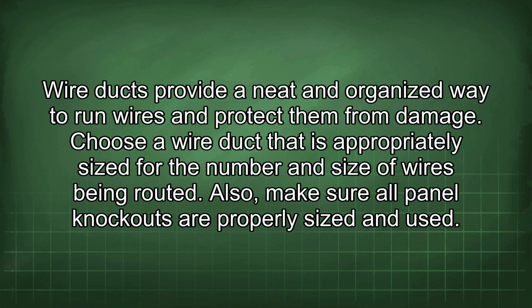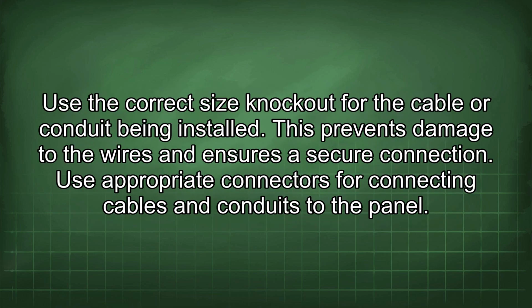Also, make sure all panel knockouts are properly sized and used. Use the correct size knockout for the cable or conduit being installed. This prevents damage to the wires and ensures a secure connection.